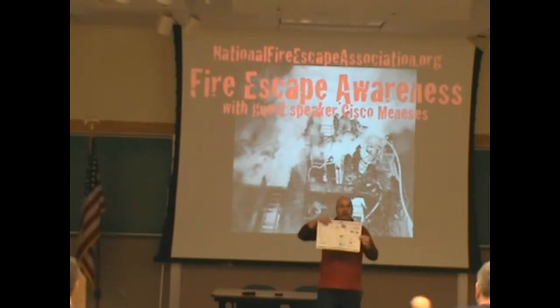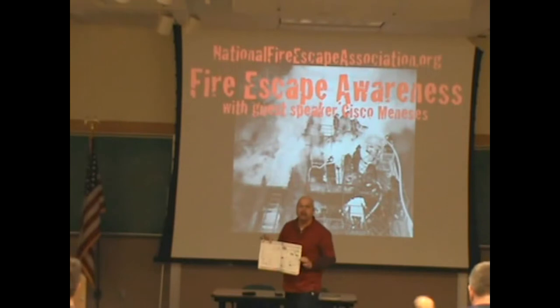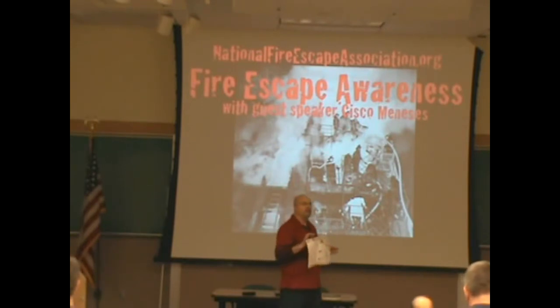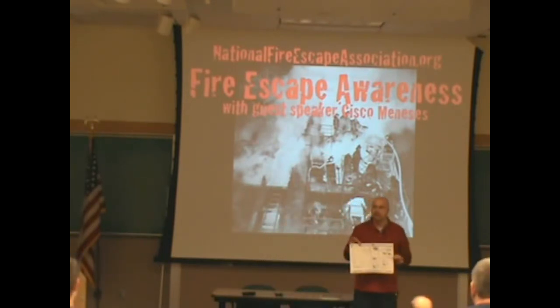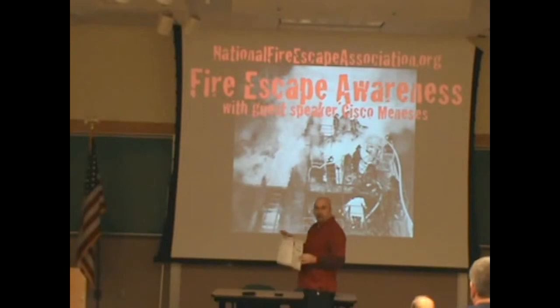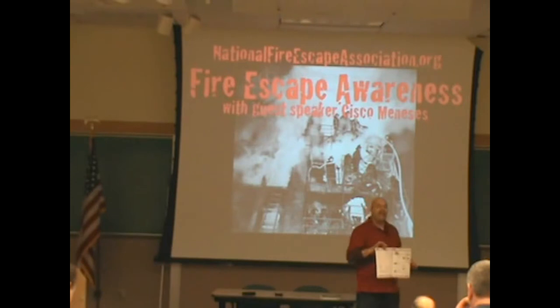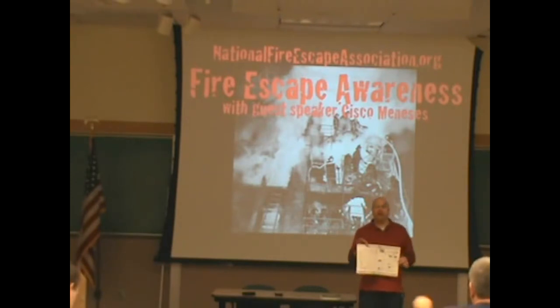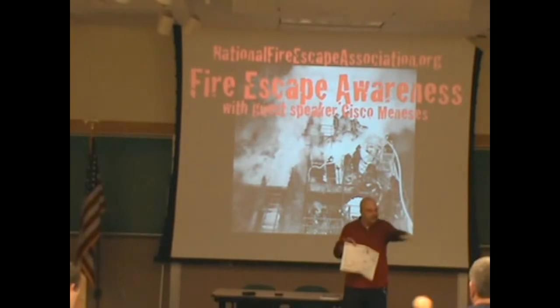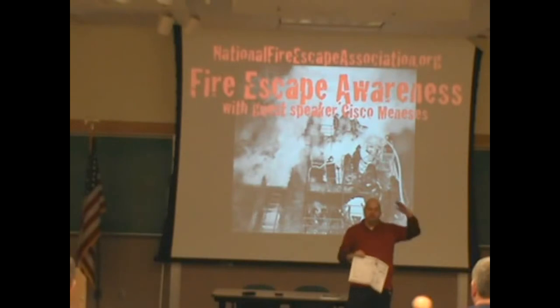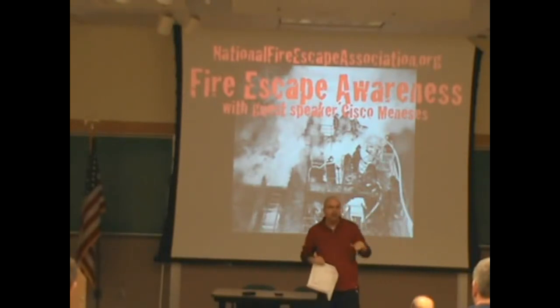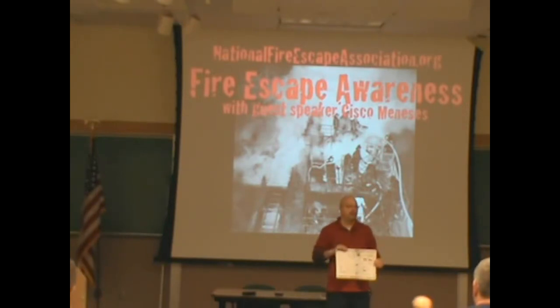All fire escapes must be complete to grade. Everybody who has a fire escape ladder that ends 8 feet off the ground — it's illegal. Back in the 40s and 50s when they built it, the code allowed you to end the ladder anywhere from 8 to 12 feet from the ground because you were providing other ways to the ground — either a balanced stair or a balanced ladder that slides down on weights. But you were never supposed to just end it there. Any fire escape examined with a ladder ending off the ground — Grandma can't jump 8 feet. You must complete it to the ground.